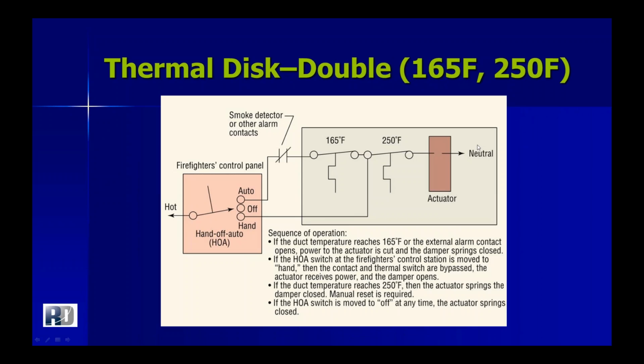Nope, this is good. But there are also thermal disks that actually have dual sensing elements for a system that's associated oftentimes with the firefighter control panel, where the firefighter control panel needs to actually allow the damper to go back open based on a human request by a firefighter. So as this is illustrating here, typically there is still the smoke detector that would have a broken contact, but there is the 165-degree element.